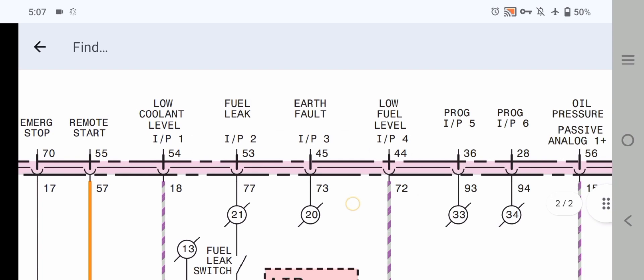Pin 70 is emergency stop output — negative input. Pin 55 is remote start. Pin 55, wire number 57, is the orange wire. Pin 54 is low coolant level. Pin 54 and pin 53 are fuel leak. Pin 45 is earth fault. Pin 44 is low fuel level going to wire 72. Also prog input 5 and prog input 6 — 'progress' meaning programmable inputs. Moving forward: oil pressure passive analog plus is pin 56.